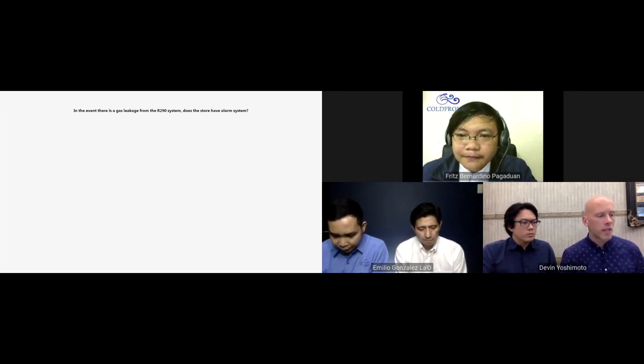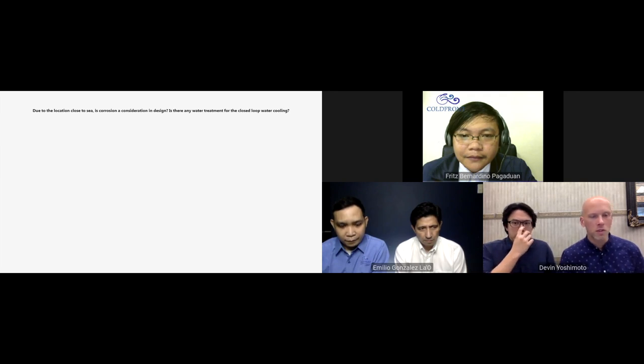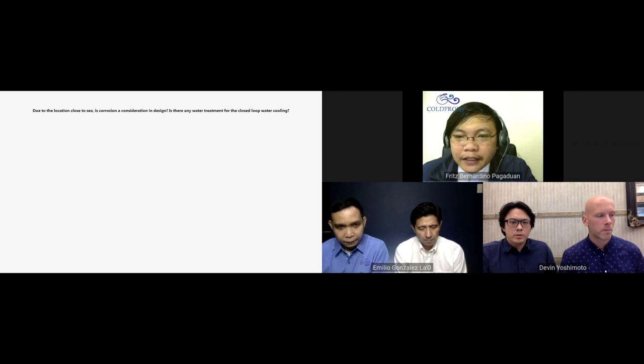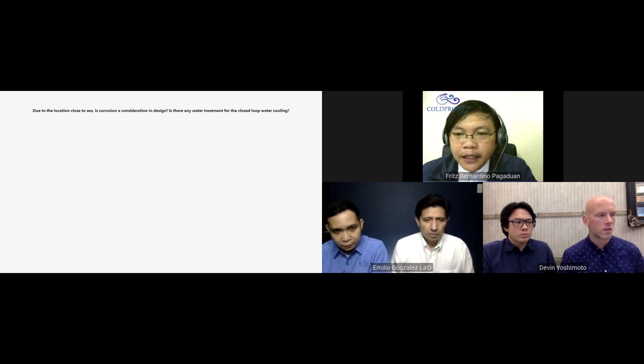Next question. Due to the location close to the sea, is corrosion a consideration in design? Is there any water treatment for the closed loop water cooling? Actually, sir, the water loop is designed as a closed loop. The principle is the same as the cooling tower, but this is a closed loop. So no foreign debris, no foreign objects, and no other chemicals except mineral water and glycol. We're not using tap water because of the oxidation inside of the system. Based on our previous project from 2017 up to now, the first water loop installation, we didn't add anything in the system. So we prevent the oxidation inside of the system because of the closed loop design.